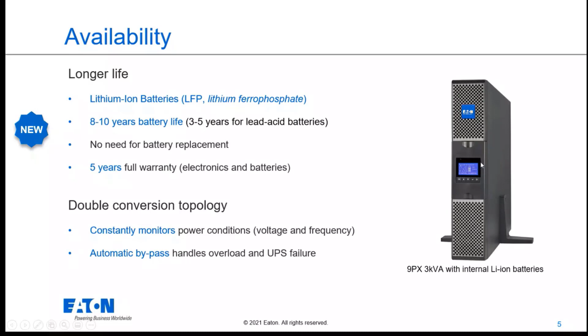Another topic linked to availability: with lithium-ion batteries we have two advantages. One is the runtime part - with internal batteries at a typical load level, say 50%, between 40 and 60, which is typical for single-phase UPS, we're able to double the typical runtime. Usually it's around 10 minutes, and with the lithium-ion solution internal batteries we can go to 20 minutes, doubling the runtime.